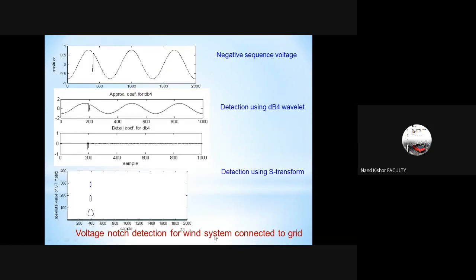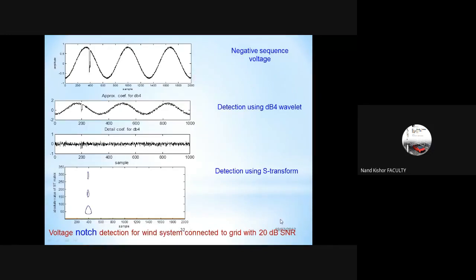Then again, we have the notch for a wind system connected to the grid. This is the negative sequence component, and then the detection using the wavelet, and the same way using the S transform, it is reflected here. And if you have the signal superimposed with noise, you can see that the mother wavelet fails to indicate the presence of the notch. However, using the S transform with the contour representation, it indicates the notch occurrence here.